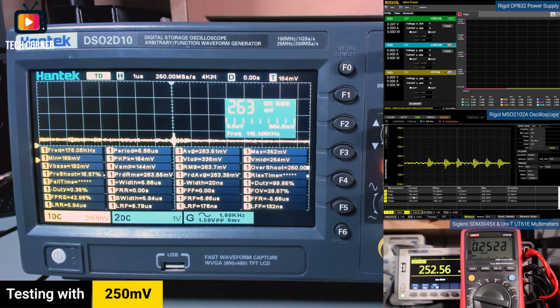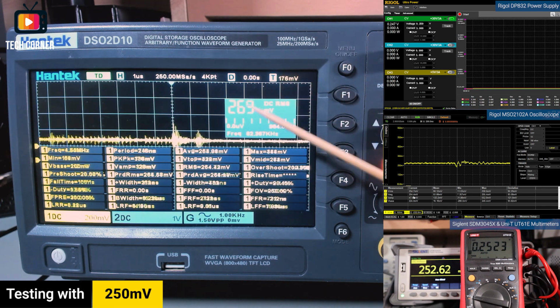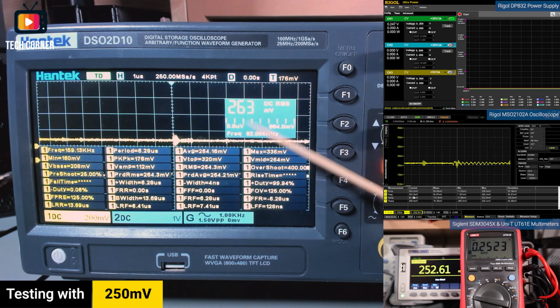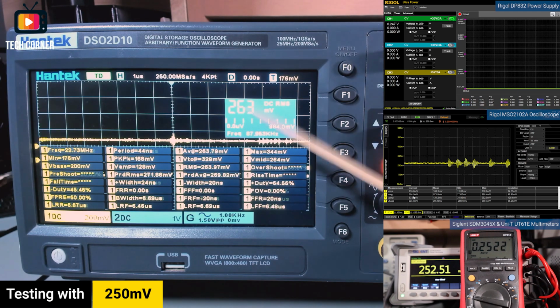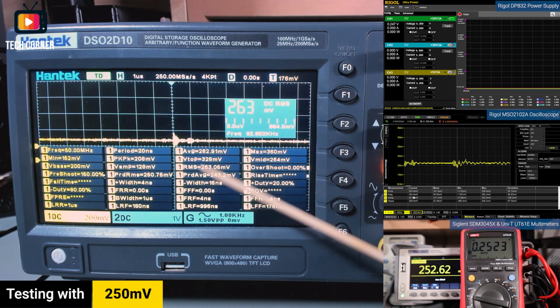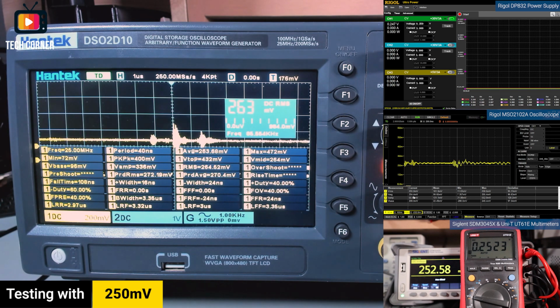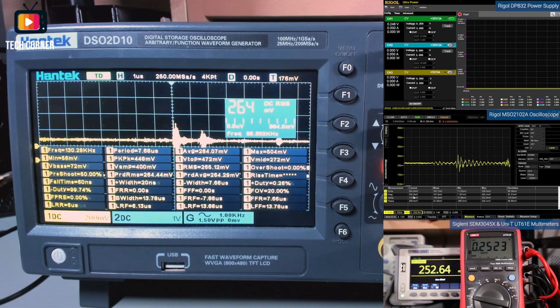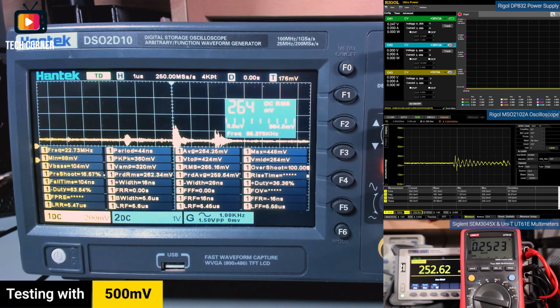The weird part on this oscilloscope, and that was my main critic on the showdown comparison of the oscilloscopes, is the auto set. When we use the auto set, the voltage will not be as near as without the auto set. I don't know why. When we change without doing the auto set, the voltage will be more accurate than after the auto set. So with the auto set we have 263 and about the same on VRMS and also average. Okay, moving on to 500 millivolts.